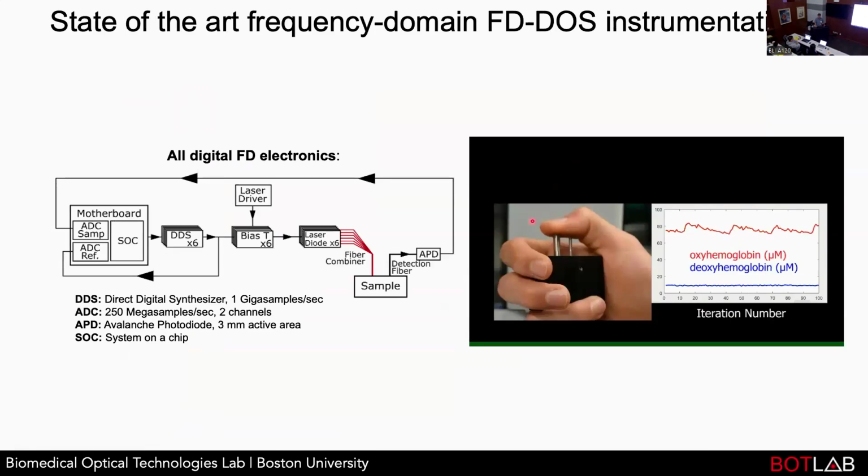In the reflectance geometry, this can happen not just with frequency domain, but with any of these techniques. If you have a change in blood volume, you have more oxygenated or deoxygenated hemoglobin, which absorbs very strongly. So maybe at systole, when you have more blood volume, your photon penetration depth actually changes. If you have more absorption, it's harder to get photons deep. They get extinguished. That means the measurement volume you're measuring is actually changing over time with each beat of the heart.